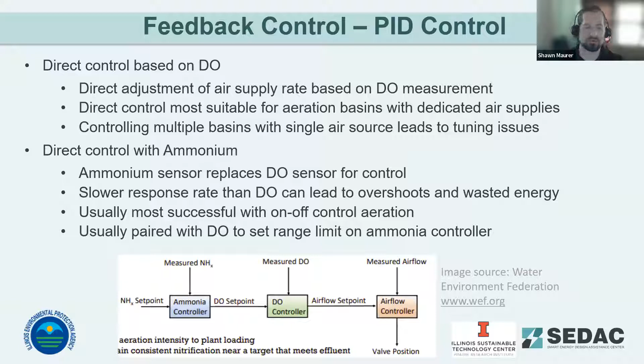But usually what we see is it's paired with a DO sensor in a cascade control. You're going to measure the ammonia as you get a differentiation from your set point. That's going to send a signal to your DO controller. The DO controller sets adjustable limits based on what the ammonium controller is requiring. That DO controller then controls the aeration system speed to maintain within those set points. This prevents the overshoots that you tend to see with direct ammonia control without a DO backup system. So you get more stable control. And again, the target here is better decreasing your nitrogen effluent, meeting those tighter regulation limits.